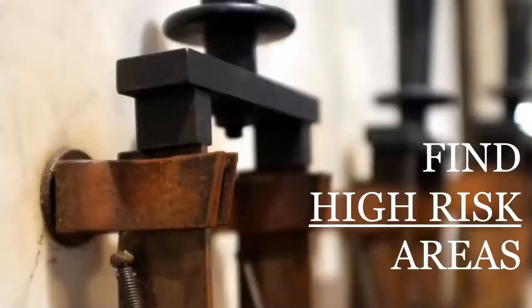The second thing that you get with an arc flash study that you can't figure out without doing it is where those high risk or high incident energy areas are. What I mean by that is, you might find you have a main breaker on a 600 volt lineup, and the incident energy on that breaker is 85 calories per centimeter squared. So up until the time you did the arc flash study, you always assumed that the 40 cal suit you were wearing was fine. But you really don't know. You're really guessing up to that point. So for me, it's those two things.